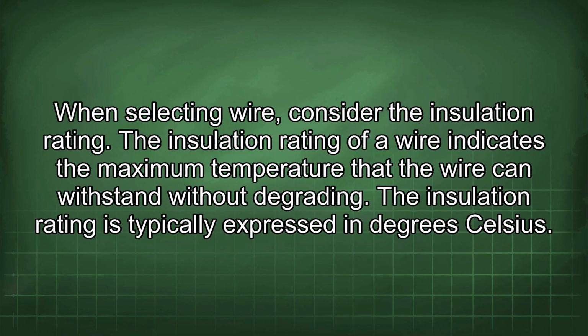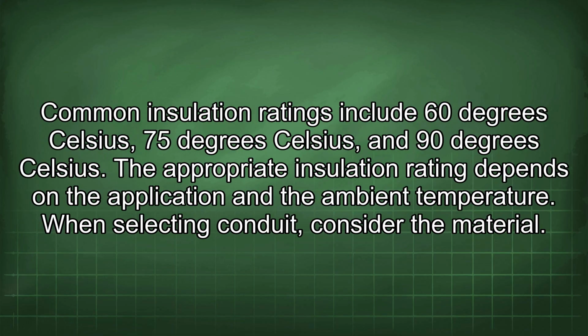When selecting wire, consider the insulation rating. The insulation rating of a wire indicates the maximum temperature that the wire can withstand without degrading. The insulation rating is typically expressed in degrees Celsius. Common insulation ratings include 60 degrees Celsius, 75 degrees Celsius, and 90 degrees Celsius. The appropriate insulation rating depends on the application and the ambient temperature.